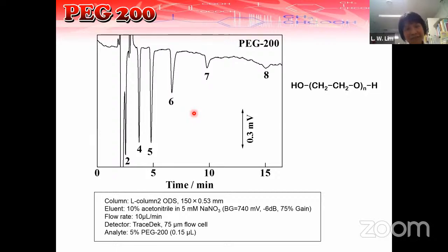because if you use a weak acid it will have a medium conductivity, the baseline will be in the middle. So whatever cations have a higher conductivity will go up, and the anions that have a lower conductivity will go down as negative peaks.